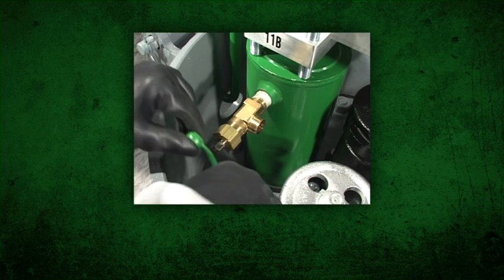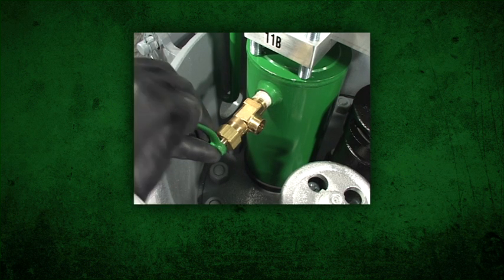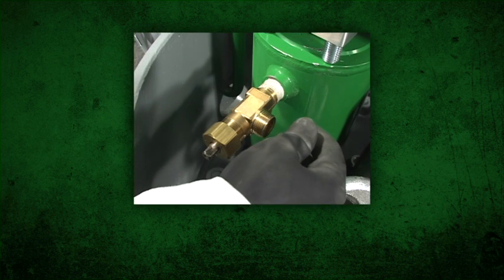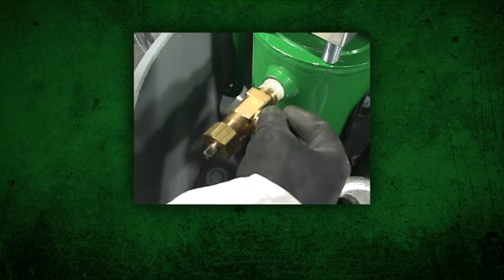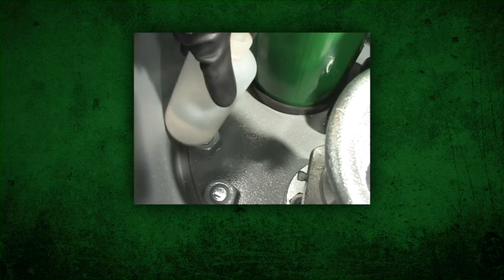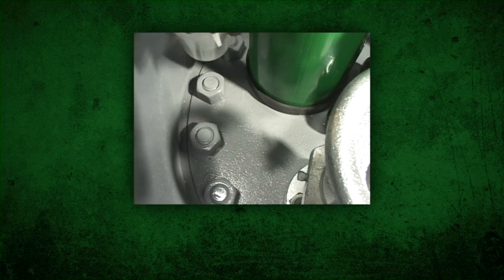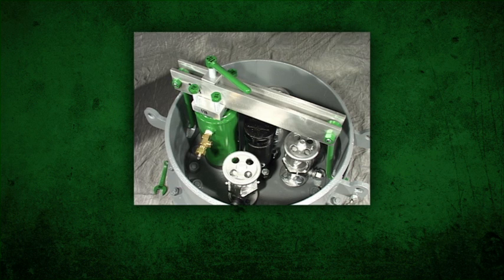Close vent valve 6V on Hood 6A1 using wrench 200C. Replace the vent valve 6V outlet cap. Test for leaks immediately after installation and at regular intervals if the capping is to be kept in place for an extended period. Most of the gasket relaxation will occur in the first hour after installation. Tighten as required to maintain the original kit seal.